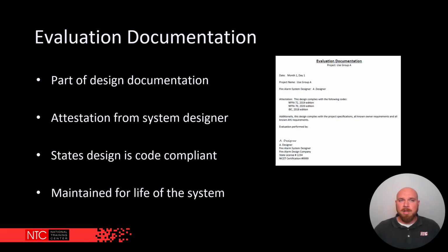Now, your evaluation document is not the same thing as the narrative. The evaluation document is part of the design documentation. It is an attestation from the designer. It states the design is code compliant and is going to tell us which codes were utilized, what editions of those codes were utilized for the design of this fire alarm system. This will also be maintained for the life of the system.